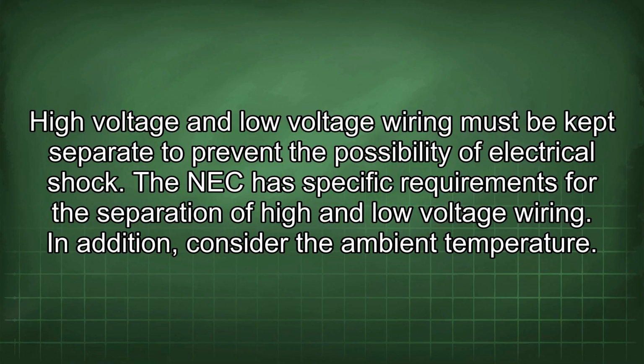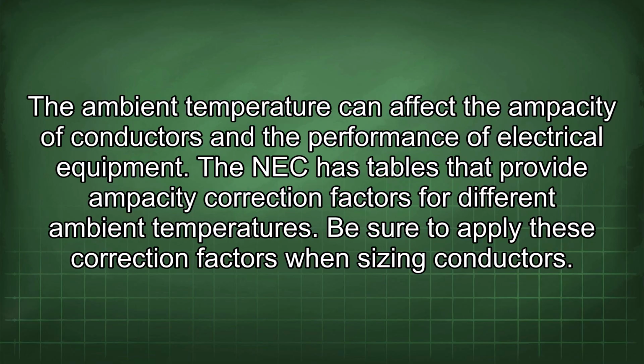In addition, consider the ambient temperature. The ambient temperature can affect the ampacity of conductors and the performance of electrical equipment. The NEC has tables that provide ampacity correction factors for different ambient temperatures. Be sure to apply these correction factors when sizing conductors.